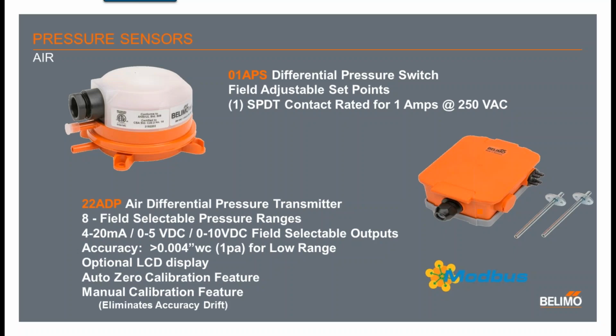Pressure sensors. Pressure sensors for air, we have a differential pressure switch, which has field adjustable set points. And we also have our air differential pressure transmitter, which has 8 field selectable pressure ranges in one single device. It also has field selectable outputs in one single device, such as 4 to 20 milliamp, 0 to 5 and 0 to 10. The high accuracy at the low pressure ranges is plus or minus 0.004 inches water column, or plus or minus 1 Pascal.